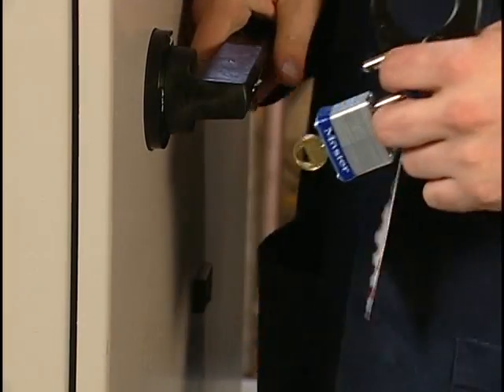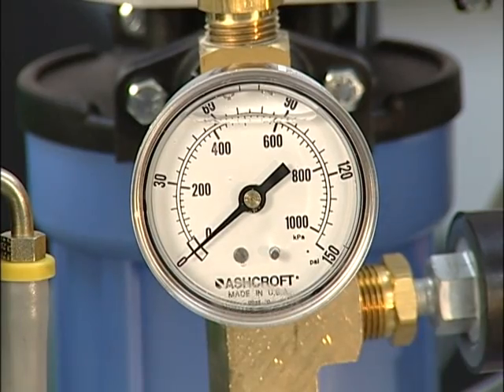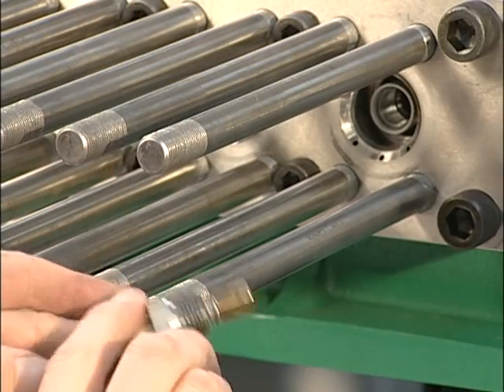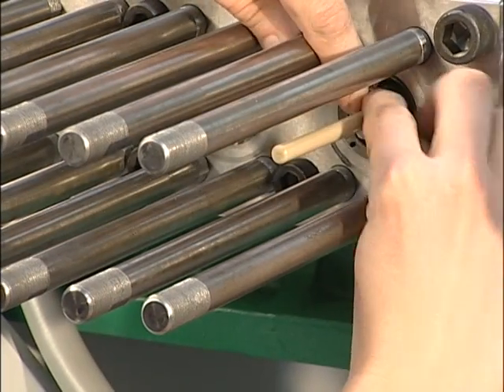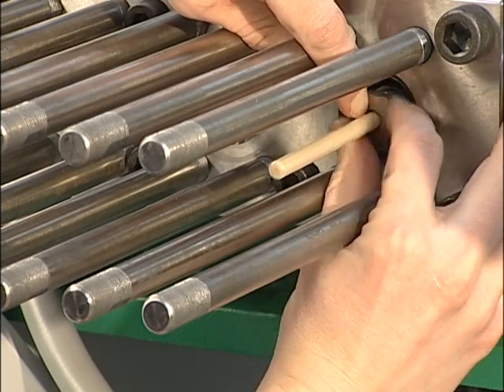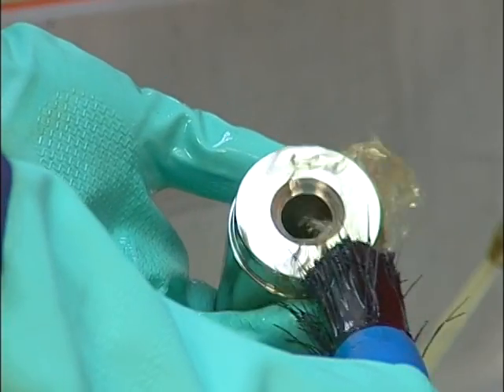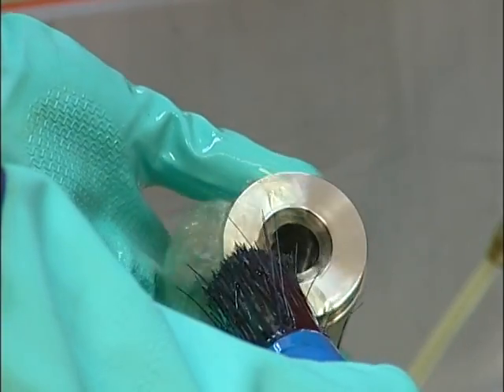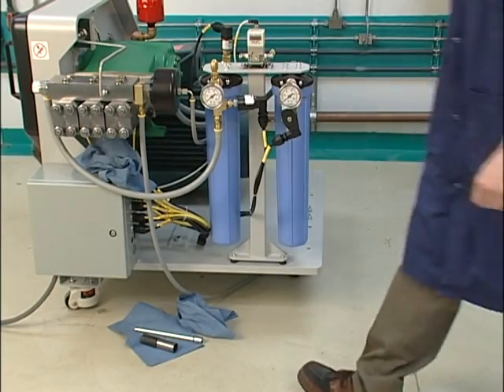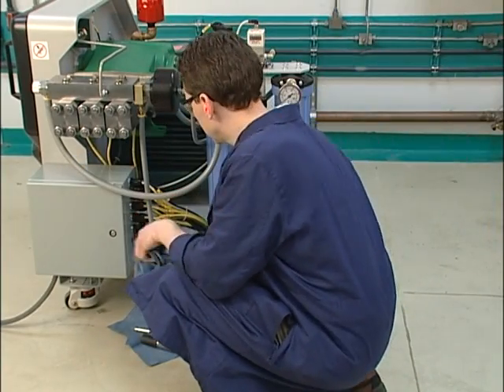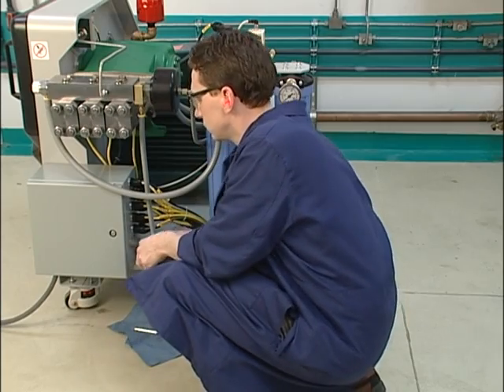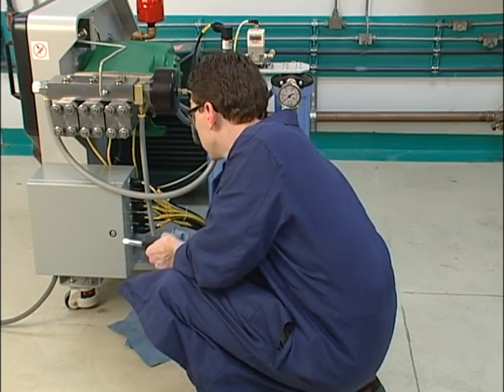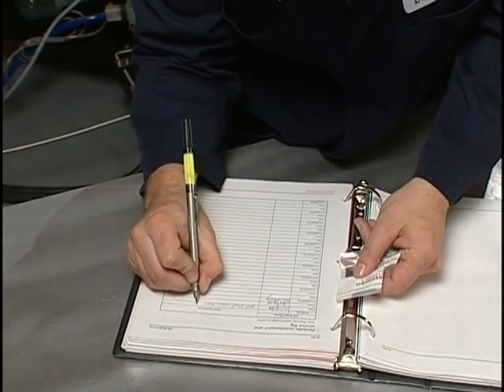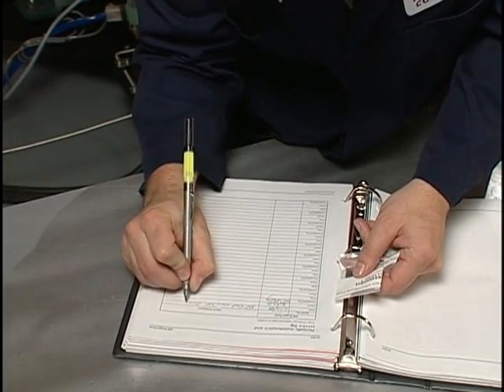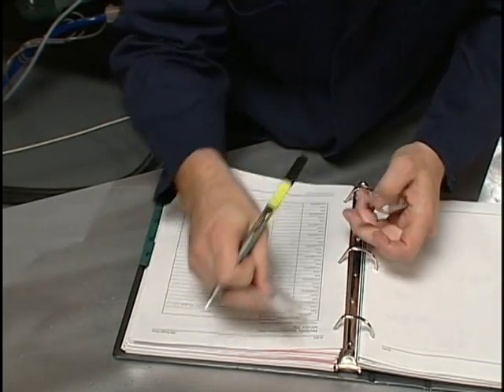Ensure the power is turned off and pressure relieved before starting any service. Handle critical parts with care and avoid scratching or denting ultra-high pressure water system components. Make sure all operating parts of the machine are clean. Inspect the area around the equipment for unnecessary parts, tools, and rags. Remove them before operating the equipment. Maintain a service log. It will provide important information to help you stock spare parts and diagnose problems.